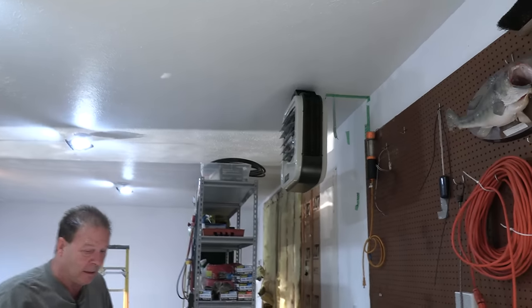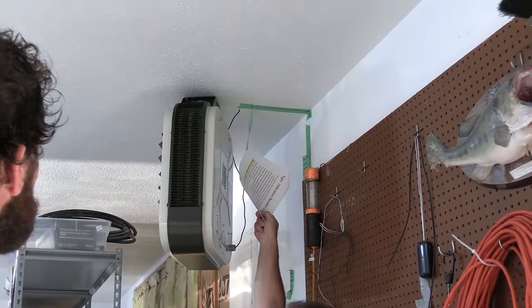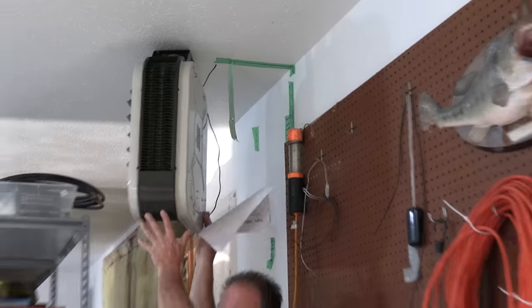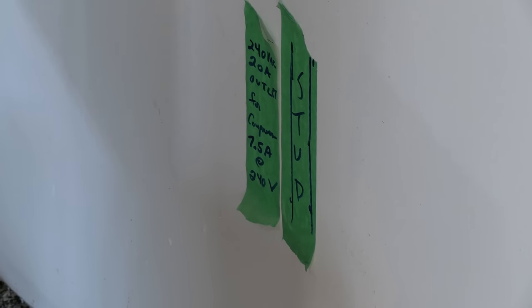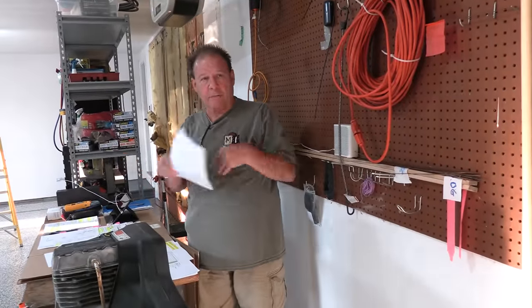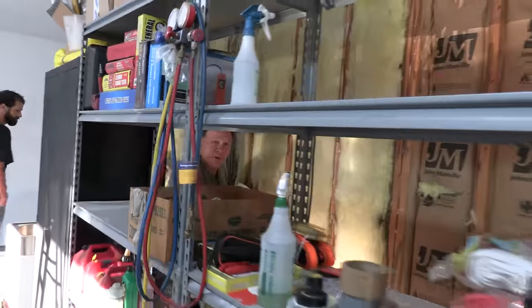If there's a way to legally come out of the ceiling, that will be far easier than trying to find your way down through the wall. That's a 240-volt circuit — one for the heater. Then there's a more traditional one: I want a 20-amp 240-volt for my compressor, and I've cut some access slots upstairs to get there. Finally the dryer circuit — it has a 40-amp breaker but we're not using it anymore. We're going to drop in a new 20-amp 120-volt circuit. Since all the drywall is out we'll just be able to pop it in from the back side.